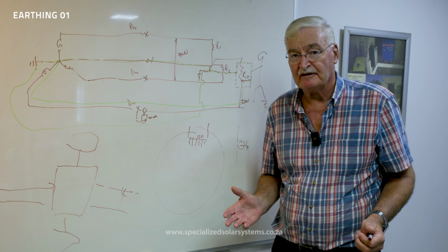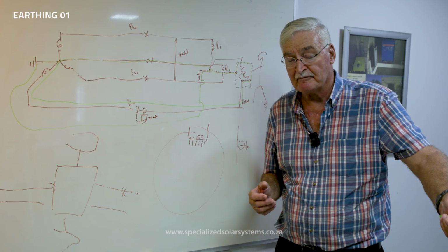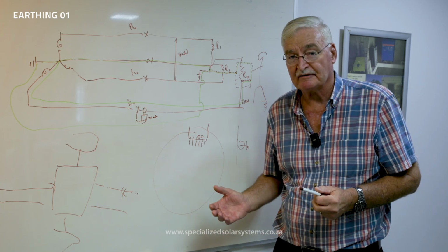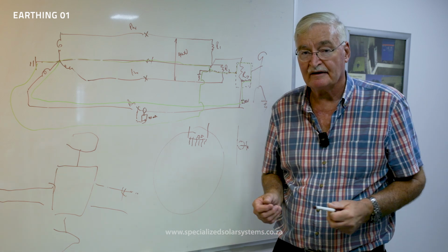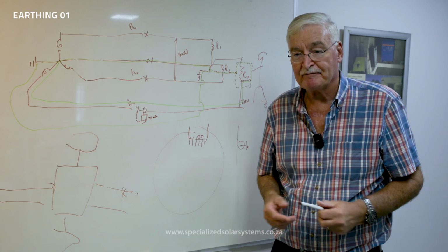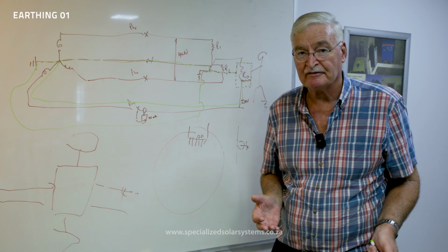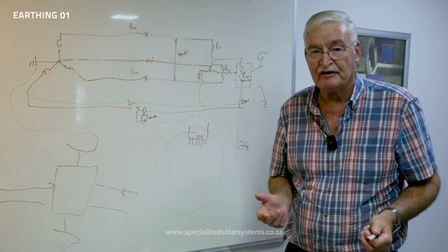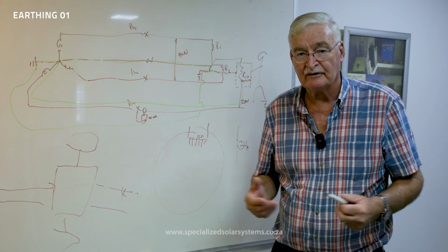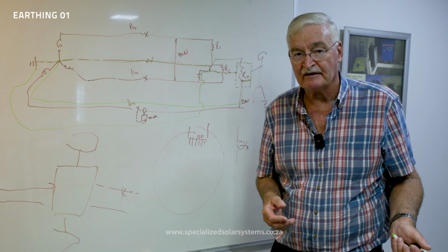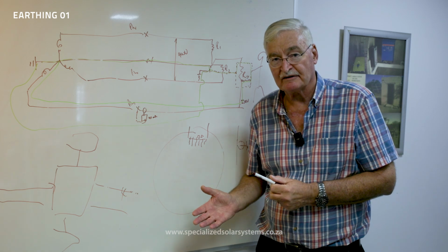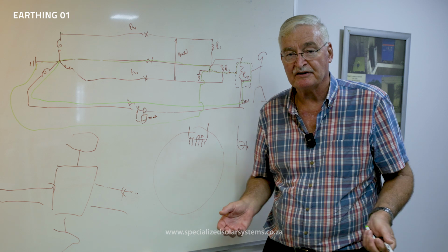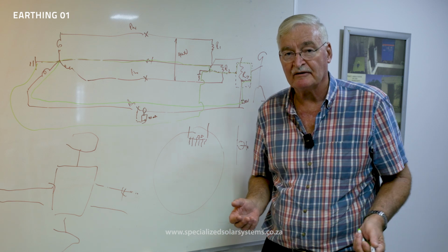The question often asked is, can you use the mains earth? Do you have to have a separate earth? In most cases I prefer to share the earth with the mains earth. I would normally have the mains earth tested, and if it's less than 5 ohms, then I would invariably decide to connect to that. But if it's not low enough, you have to create additional earthing through earth spikes or a trench earth, and I normally bond it to the mains earth.